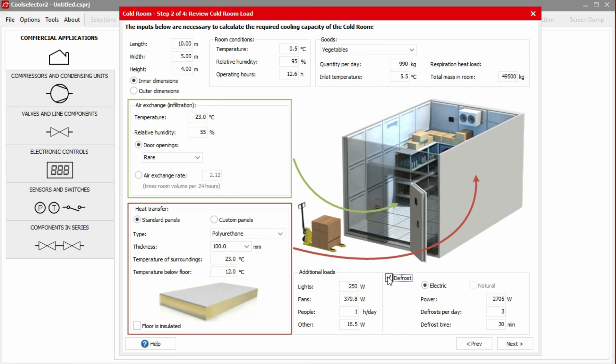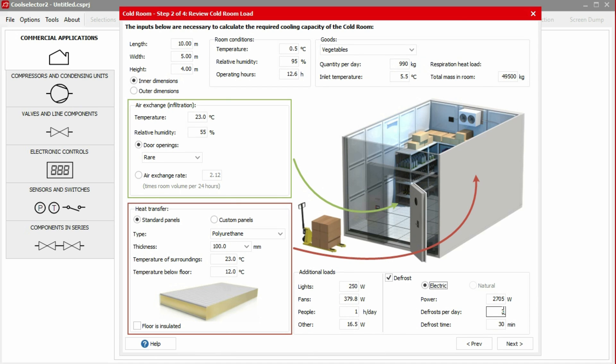Next, we have the option to include or exclude defrost. For defrost, we have the option to have electric or natural defrost. Natural defrost isn't possible at low internal temperatures, so we'll select electric defrost. The room is rarely opened, so we can also assume a low number of defrosts. In this example, we'll assume only one defrost per day. We keep the defrost power and time as default, and then we select next to continue.